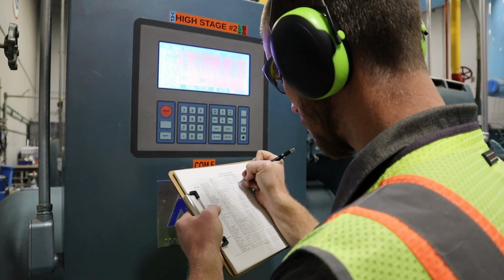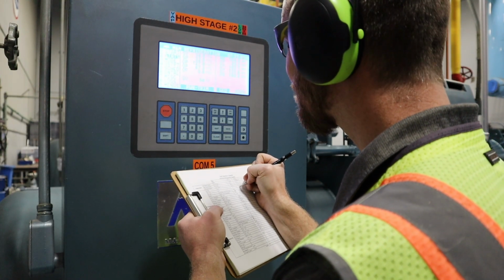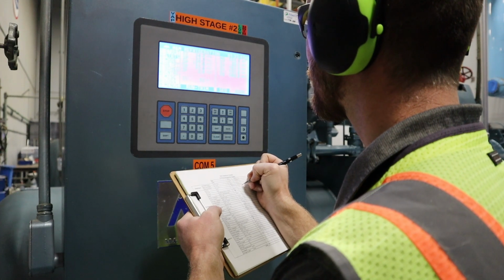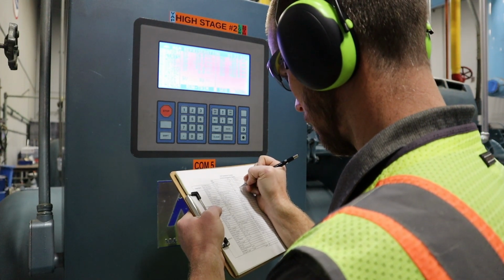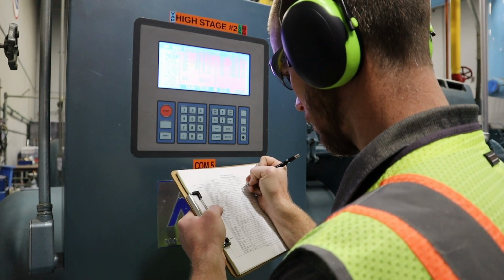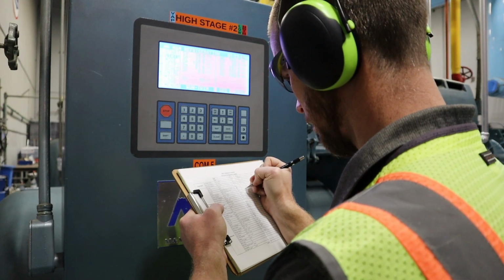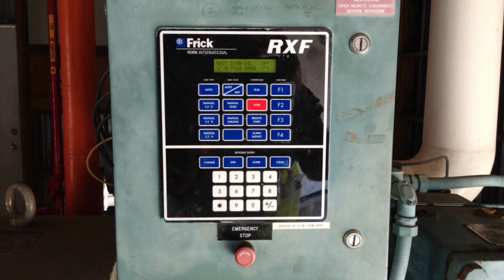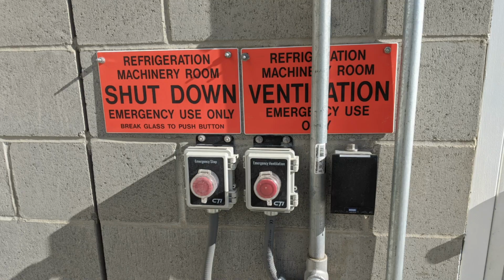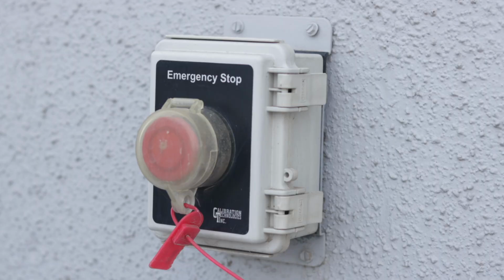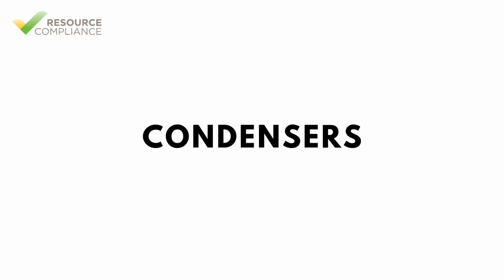When a compressor is in auto mode, it will shut off automatically based on the system's suction pressure. Operators can shut off a specific compressor at the PLC HMI or directly from the compressor control panel. In an emergency, an e-stop on the compressor panel can be activated. Alternatively, the system e-stop, which is typically located outside the machinery room, can be used to shut down all compressors at once. The condenser must be running before any compressor is started.